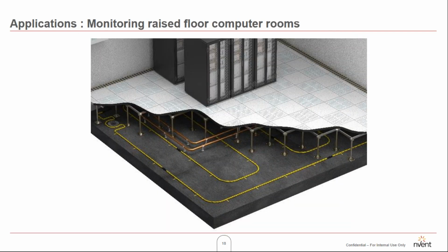Depending upon the type of hazard present, if there are pipings which are running underneath the raised floor or above the false ceiling, we can design a water leak detection system. We can also install a water leak detection system in the intermittent space between the perimeter of the room, provided there is a potential water leak hazard present in there. So designing of the system depends upon the threat perception from where the water leak can come in, and accordingly laying of the sensor is chosen.